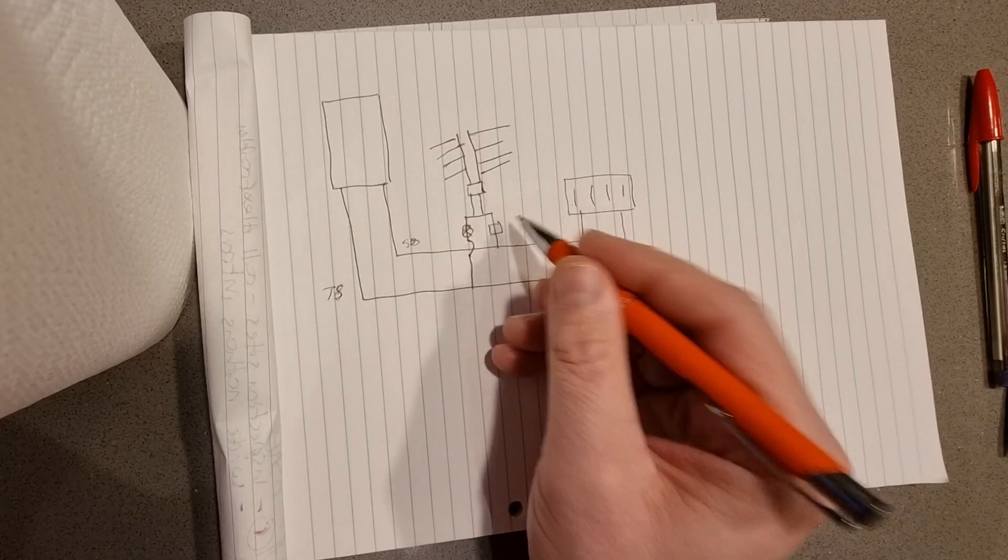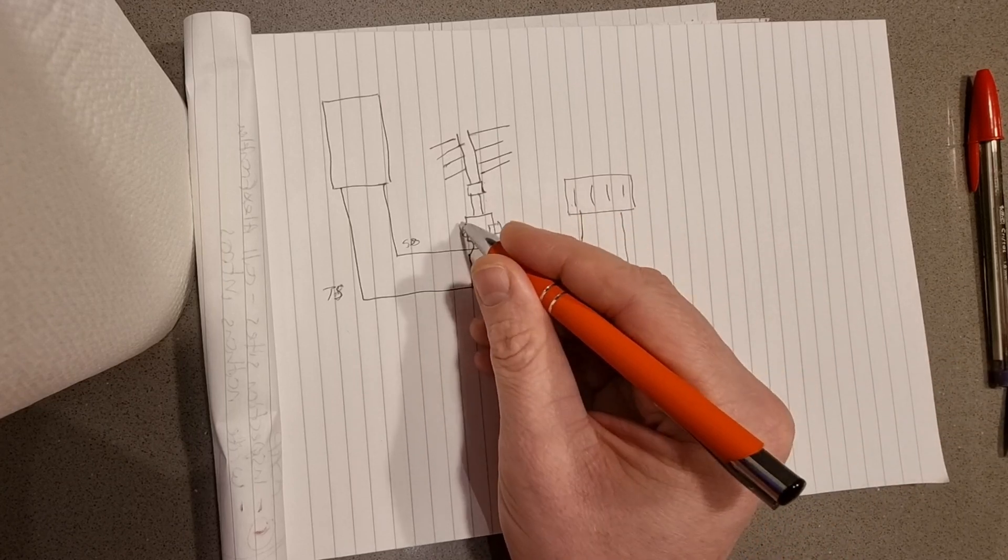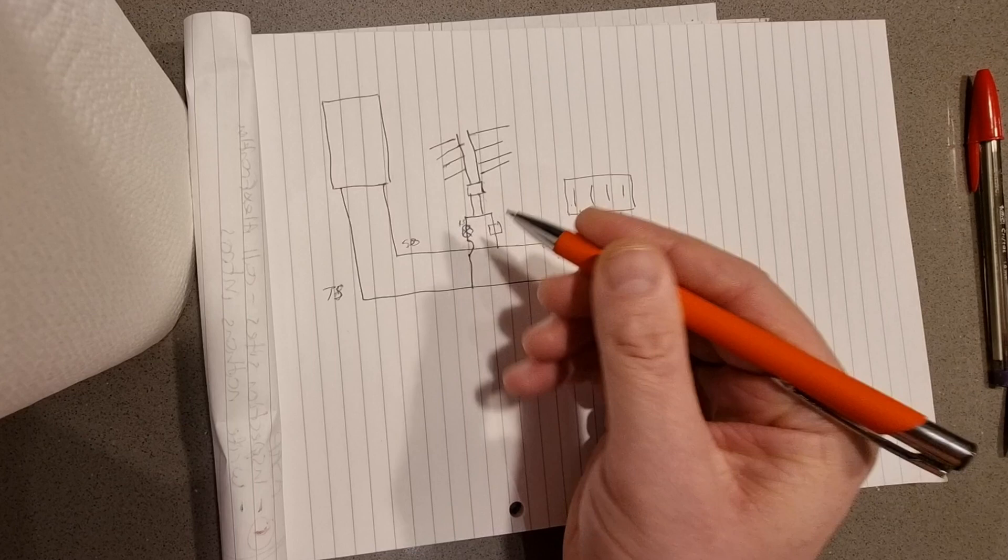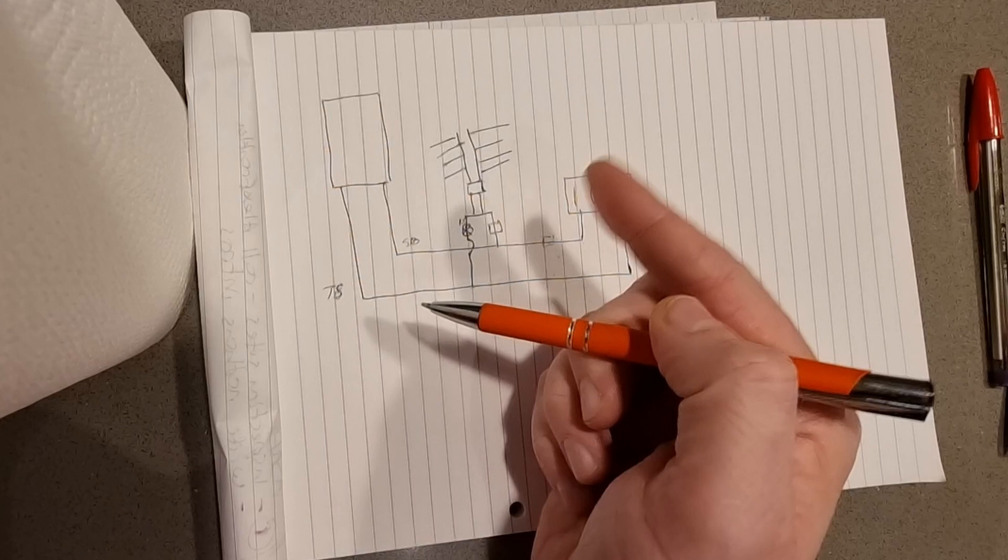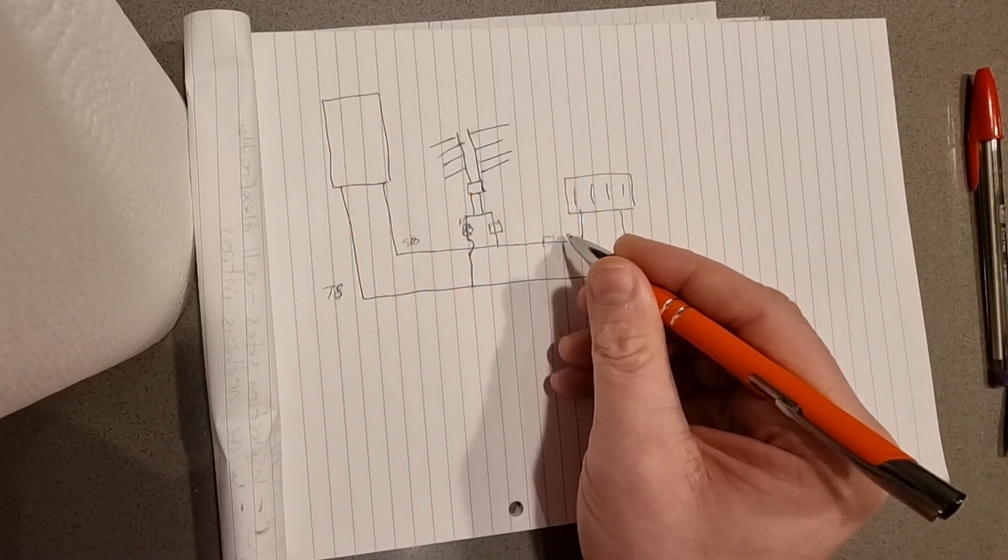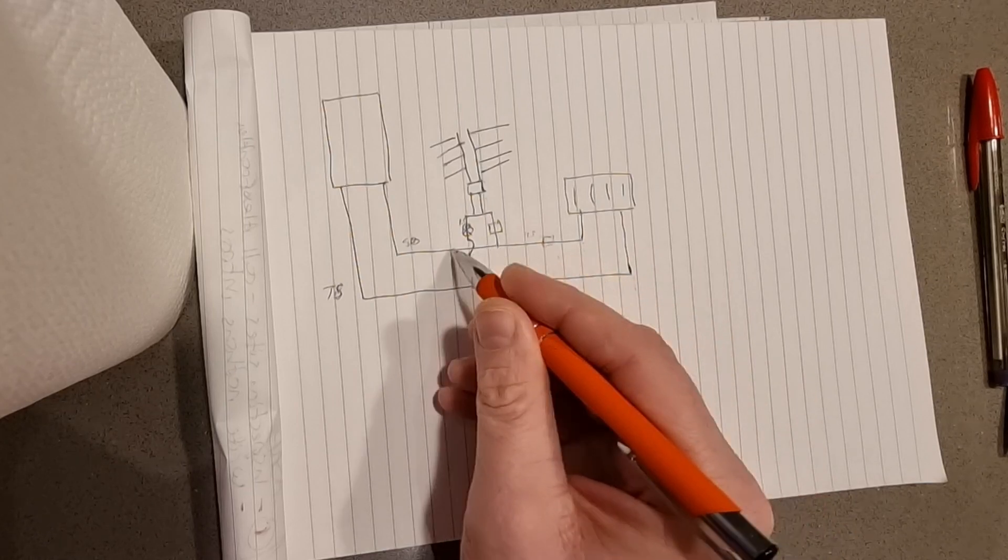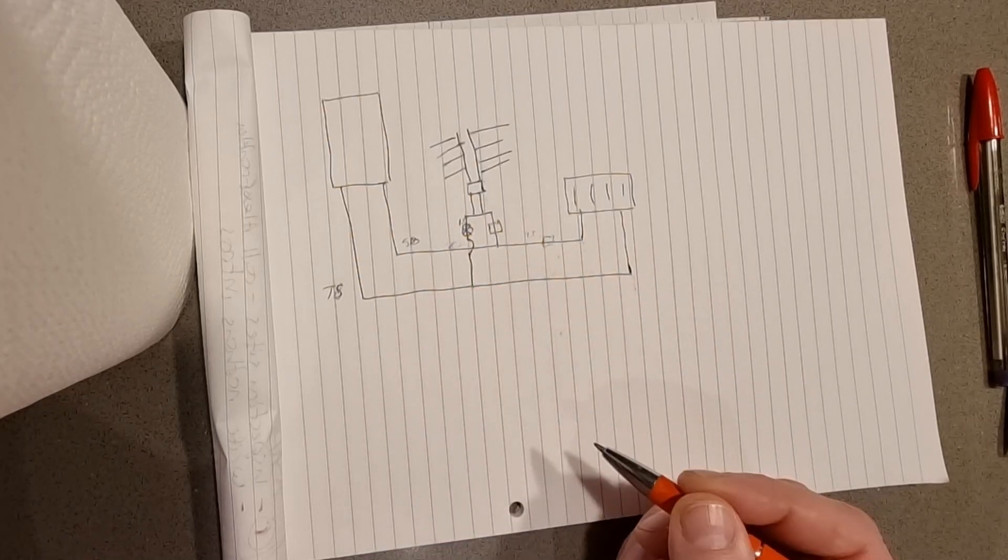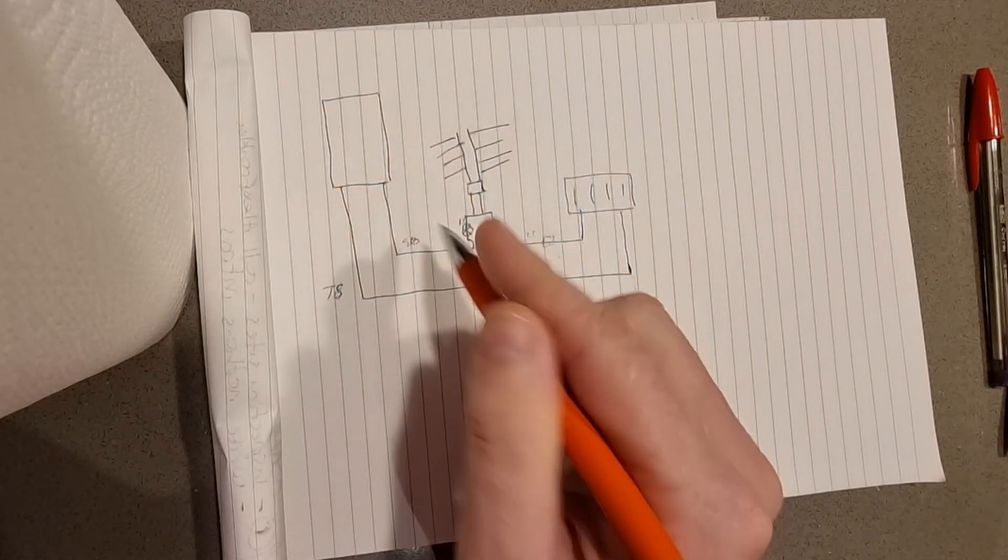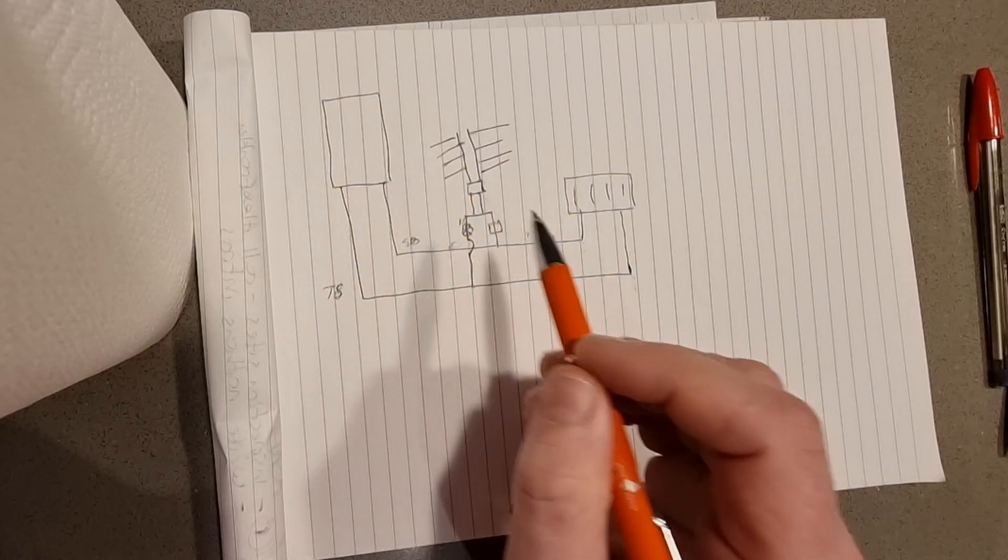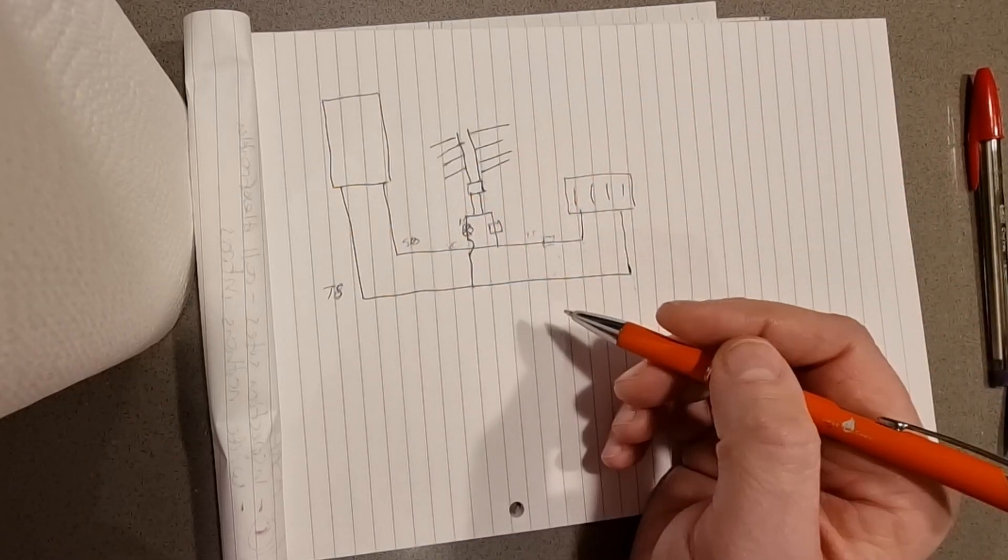The boiler will respond to the demand. This loop will increase in DT. So this loop might increase to DT15—it's increased flow rate relative to its output. If that's gone to DT15 but the boiler pump's stepped back, this flow rate will be lower. So this might go up to DT25, and the result is they cancel each other out and have a DT of 20 again at the boiler. So the boiler doesn't stop condensing. You cannot avoid mass flow, and the boiler typically has either a burner-linked pump or a DT pump.